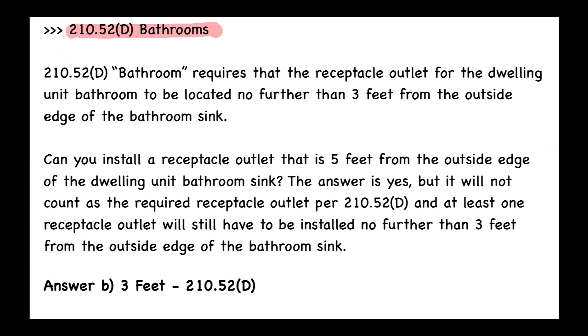Summarizing from the textbook: 210.52(D) requires the receptacle outlet in a dwelling unit bathroom to be no further than three feet from the outside edge of the bathroom sink. You can install a receptacle outlet beyond five feet, but it won't count as the required outlet — at least one must still be within three feet. The answer is B, three feet, per 210.52(D).